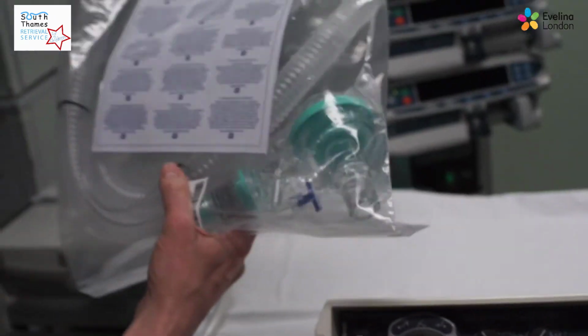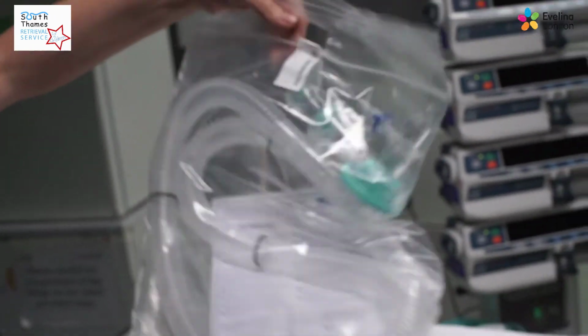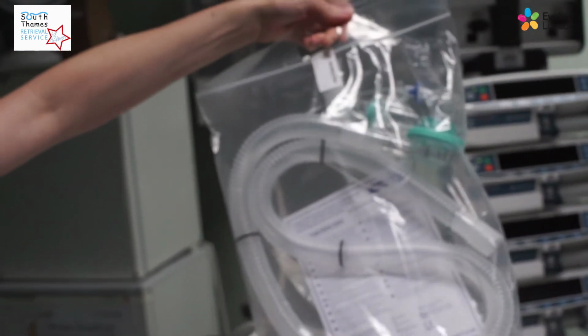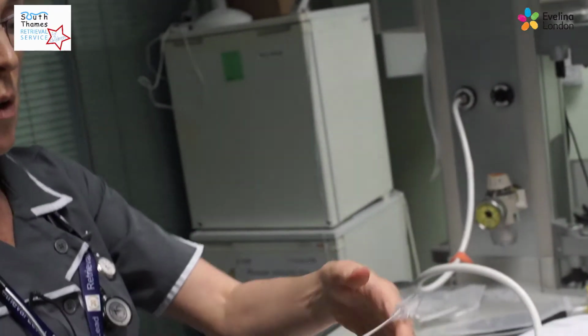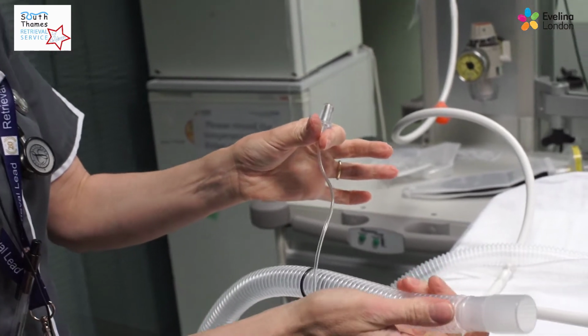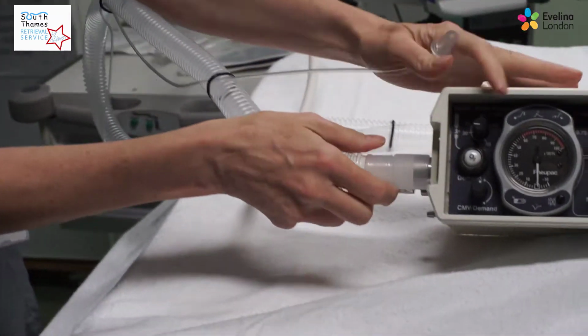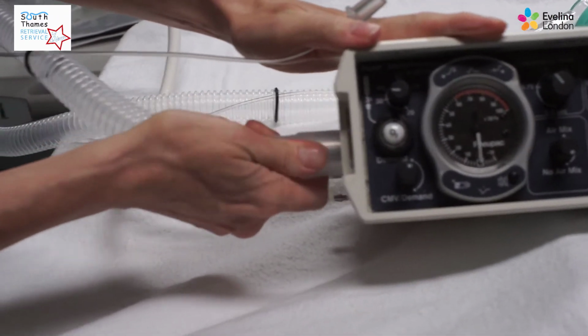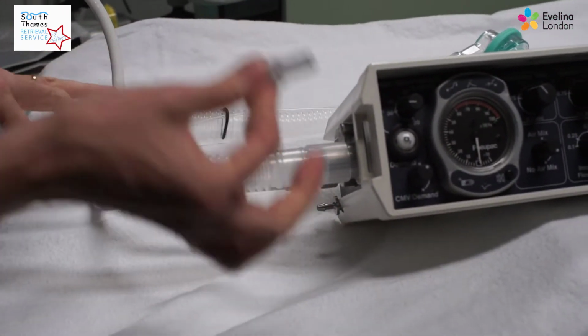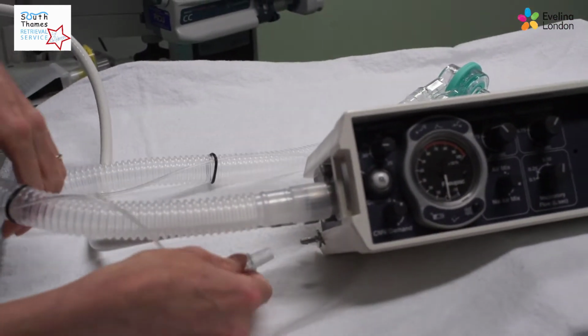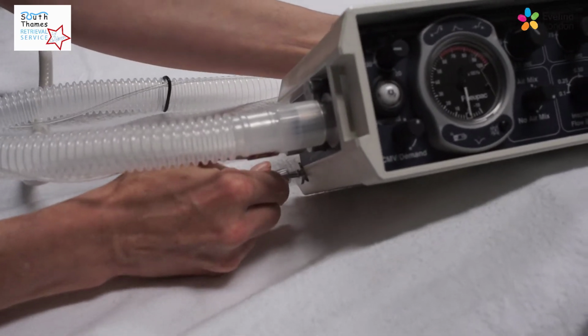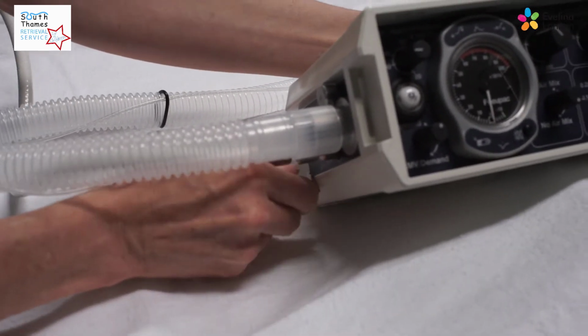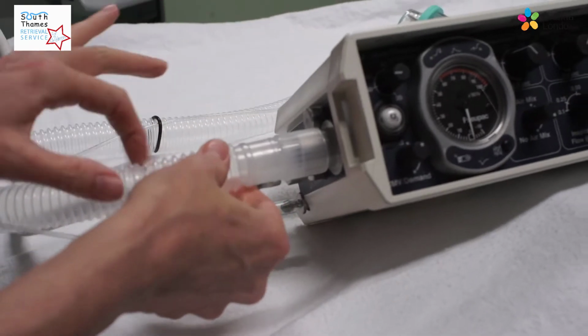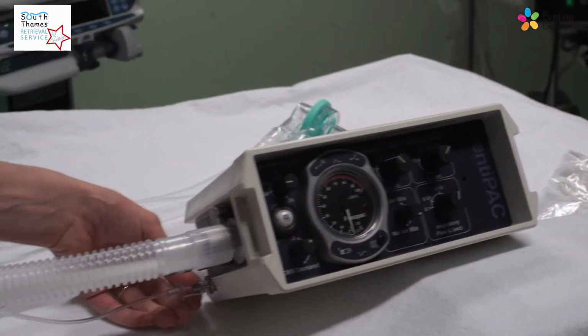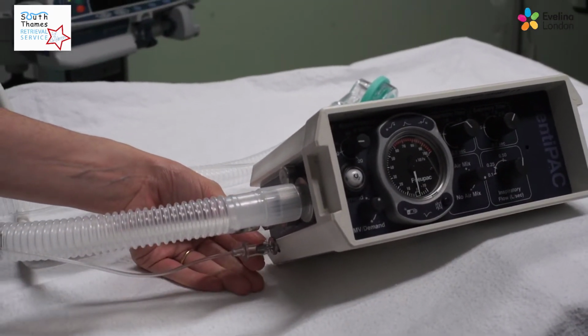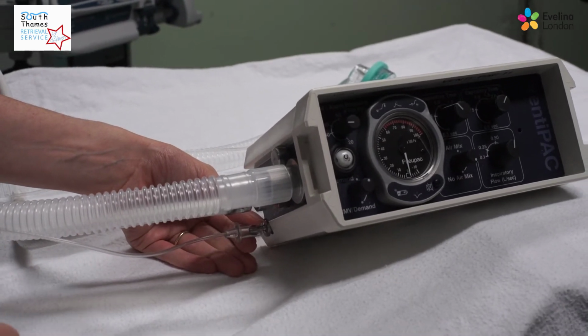First of all, I'm going to attach the tubing, and VentiPAC tubing comes all together in a sealed pack. When assembling the VentiPAC, it's important to secure the larger tubing onto the exit port, and then this smaller piece of tubing goes to the back, and that will measure the pressure that the ventilator is delivering. The ventilator can function without the pressure line being secured, but you won't get a reading of the pressures you're delivering.